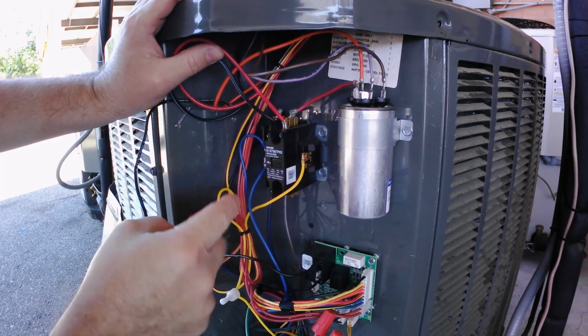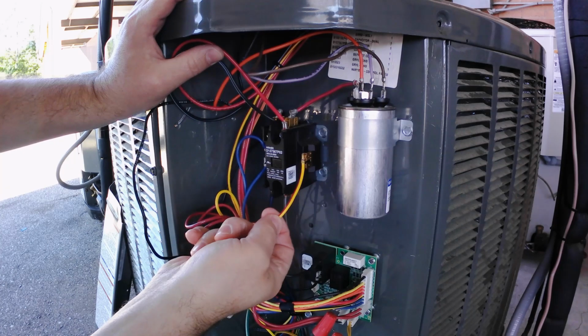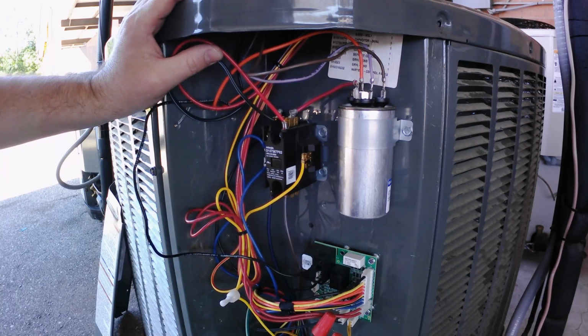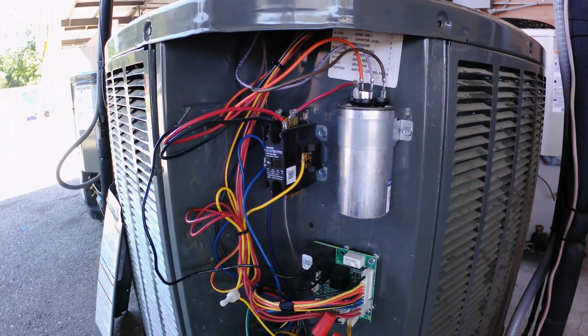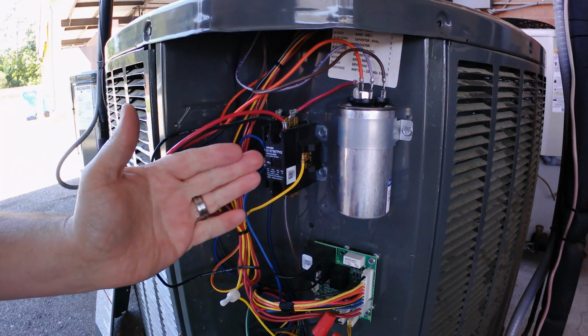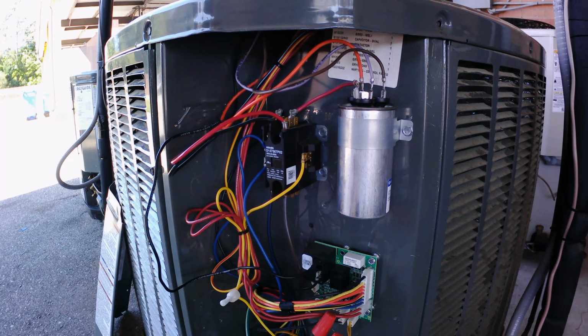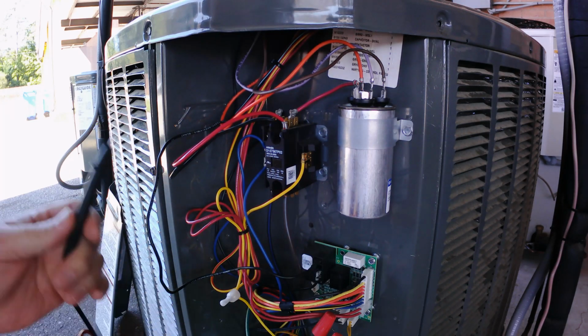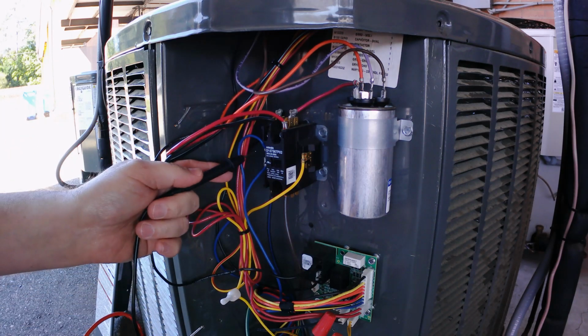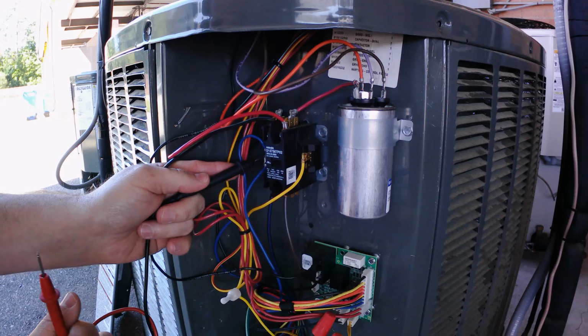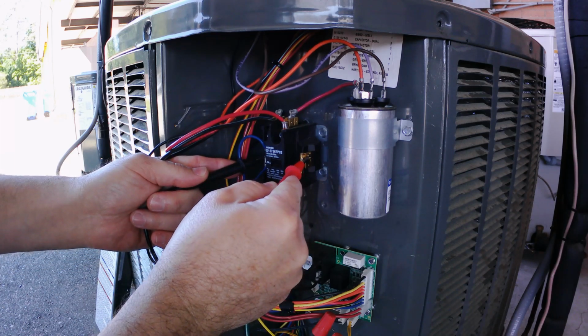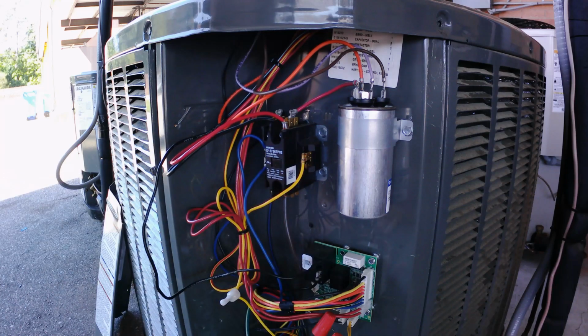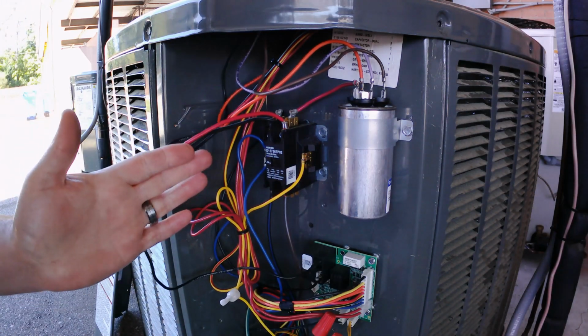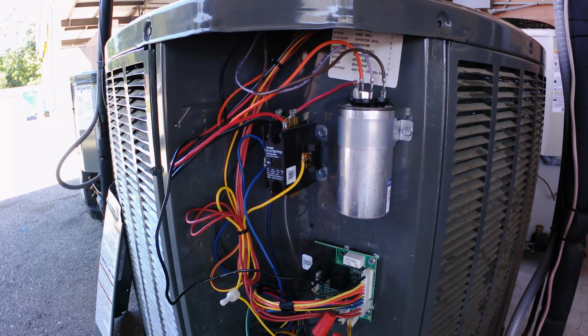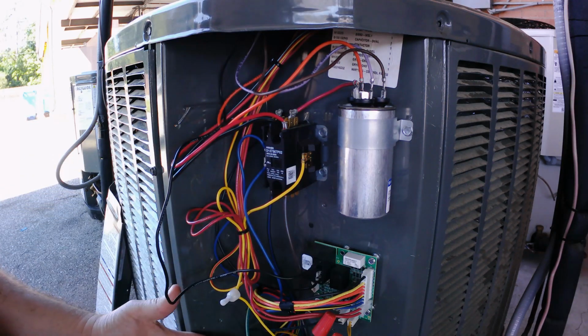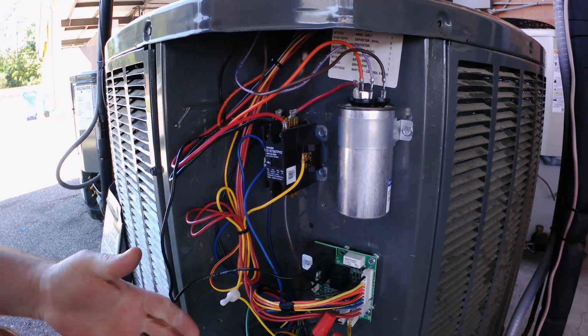The side of the contactor in this case is pretty much color coded. The Y is here and your common is on the other side, so it's the side terminals. But like I said, in the case of a contactor, this is pretty much a normally open switch. This particular Trane unit has a single pole contactor. So if I'm coming out here and the outdoor unit's not running, one of the first checks I'm going to do is to the side of the contactor, and I've got, in this case, 0 volts. So what that means is the low voltage hasn't energized that coil yet. So I would then backtrack maybe to the wire nut connections for the defrost board or further back.